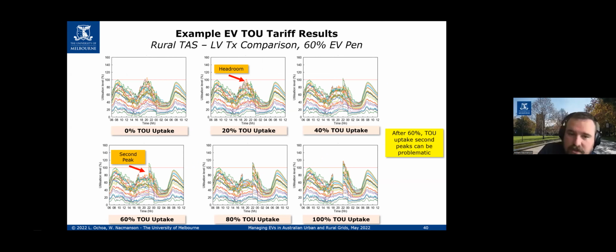So what we're showing here now is a snapshot in time, if you like. We're looking at a 24-hour period, at one feeder, rural Tasmania, one type of asset, the LV transformer utilization, and just one EV penetration, 60%. These 6 plots show the different uptakes of time of use. Because we're not focusing on the cost required to move demand, we're not considering price elasticity. It's more of a sensitivity analysis: if we got 20% of our customers to move their demand, what would that look like?